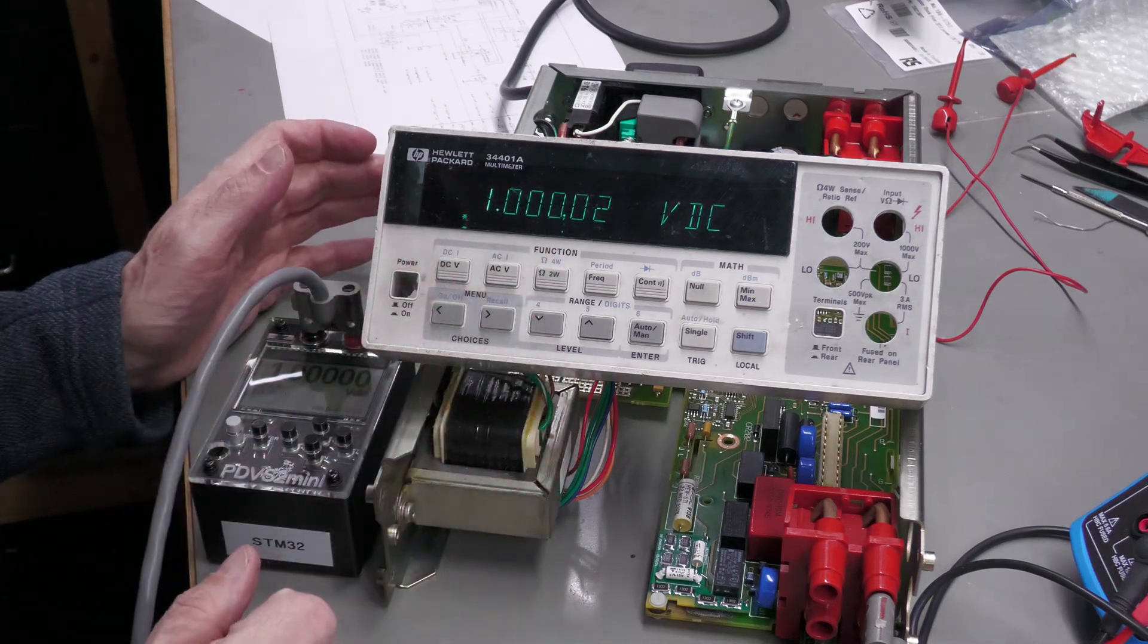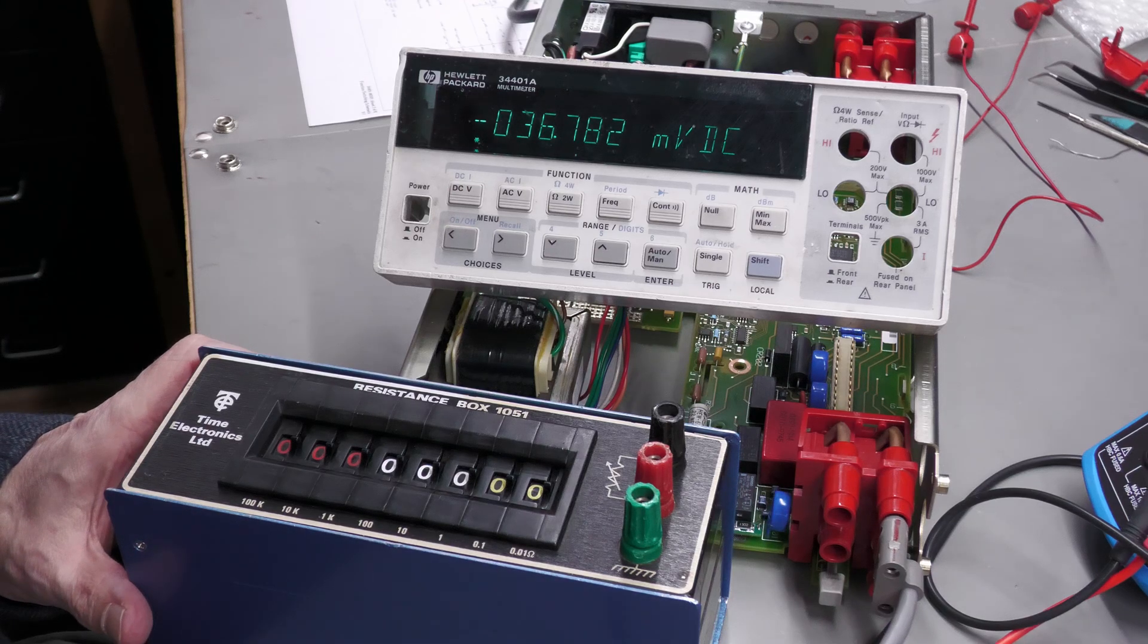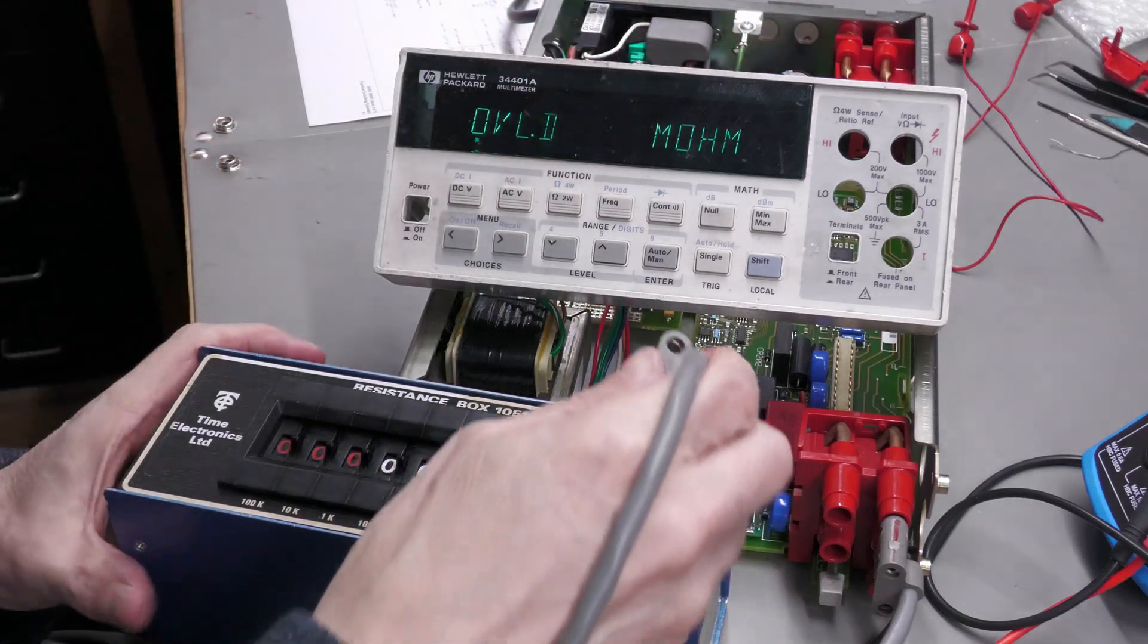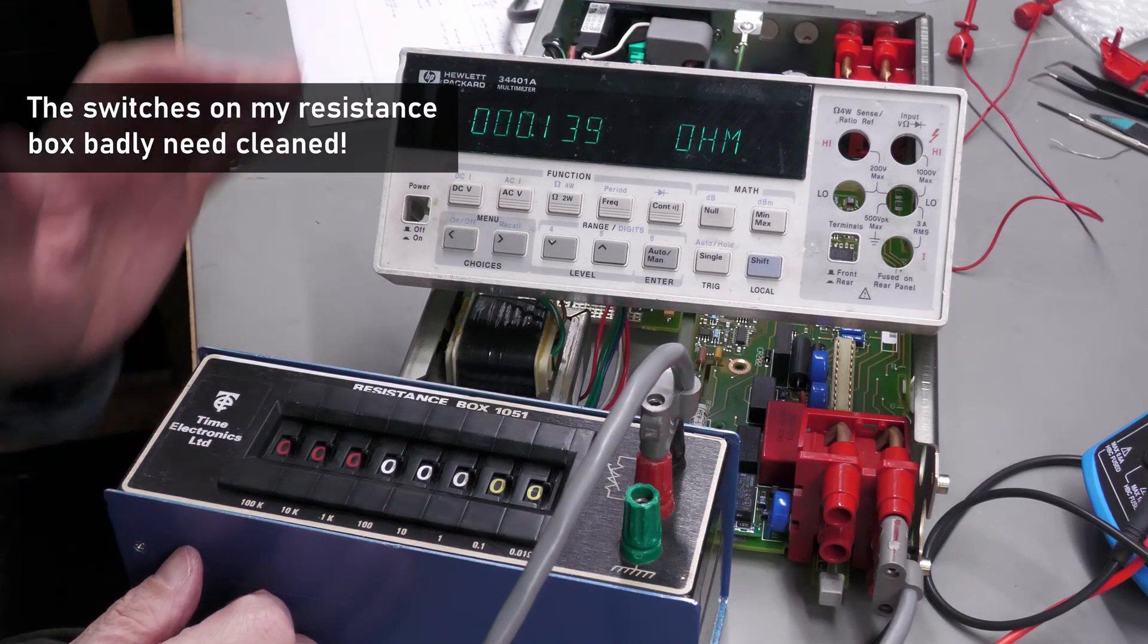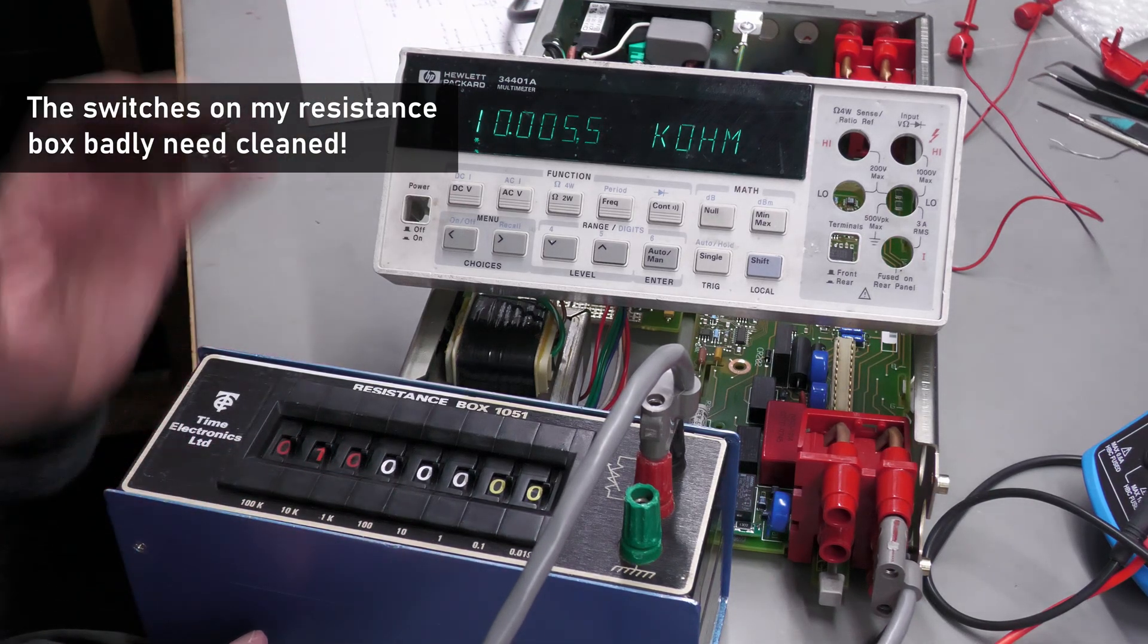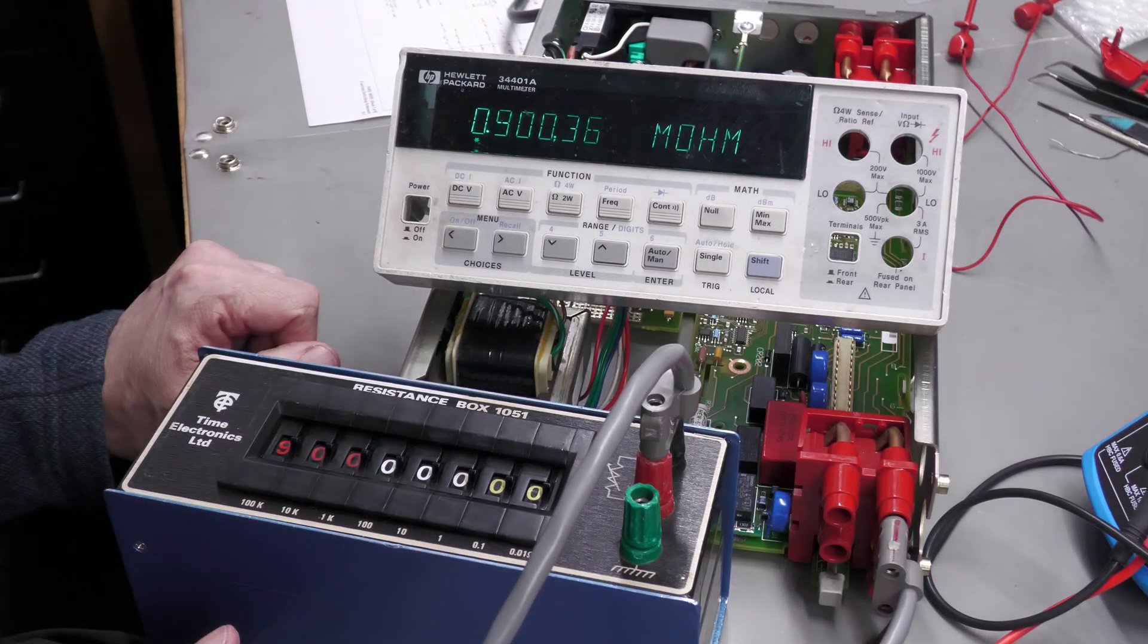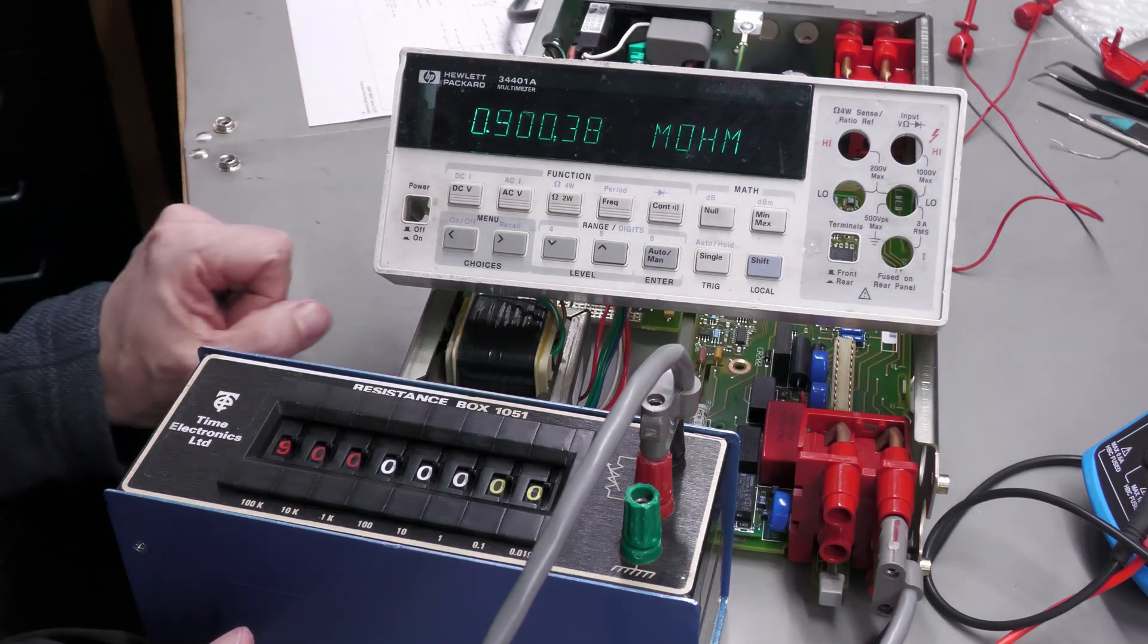Now I want to try resistance mode as well. Okay, let me try my resistance box here. Put it in two wire mode. Dead short. Yes, 0.1 of an ohm. Let's just go to 10k. Yes, that's working as well. Wow. 900k. Yes, 0.9 of a mega ohm. Resistance mode is working.